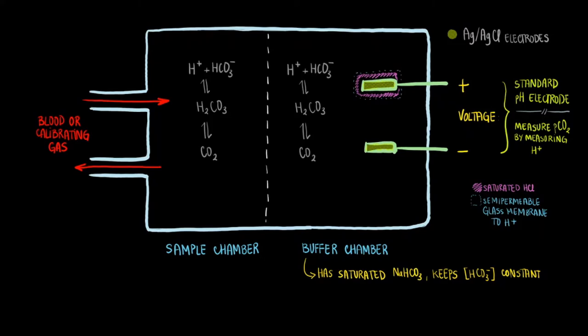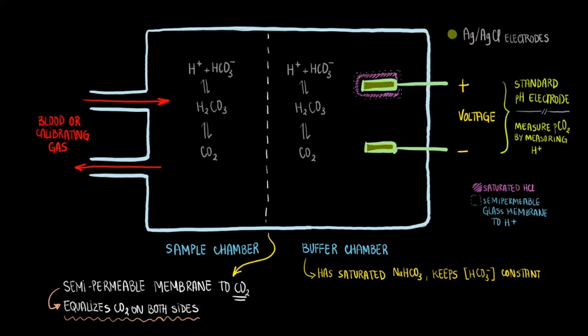Finally, the membrane that separates the sample chamber from the buffer chamber is also semi-permeable, but it is semi-permeable only to carbon dioxide. That is, carbon dioxide levels are equalized between the sample chamber, which has the CO2 level we want to measure, and the buffer chamber, which we will use for our measurements. Carbon dioxide molecules can then diffuse freely through the membrane and between the two compartments via free diffusion. This also means that you should expect the concentration of carbon dioxide to be equal between the two compartments.